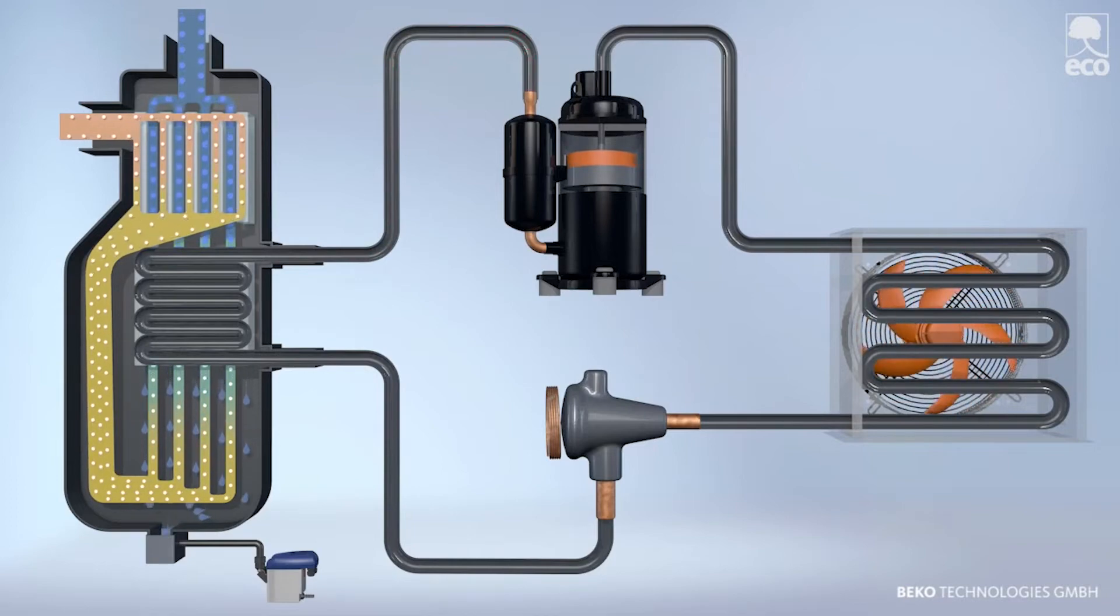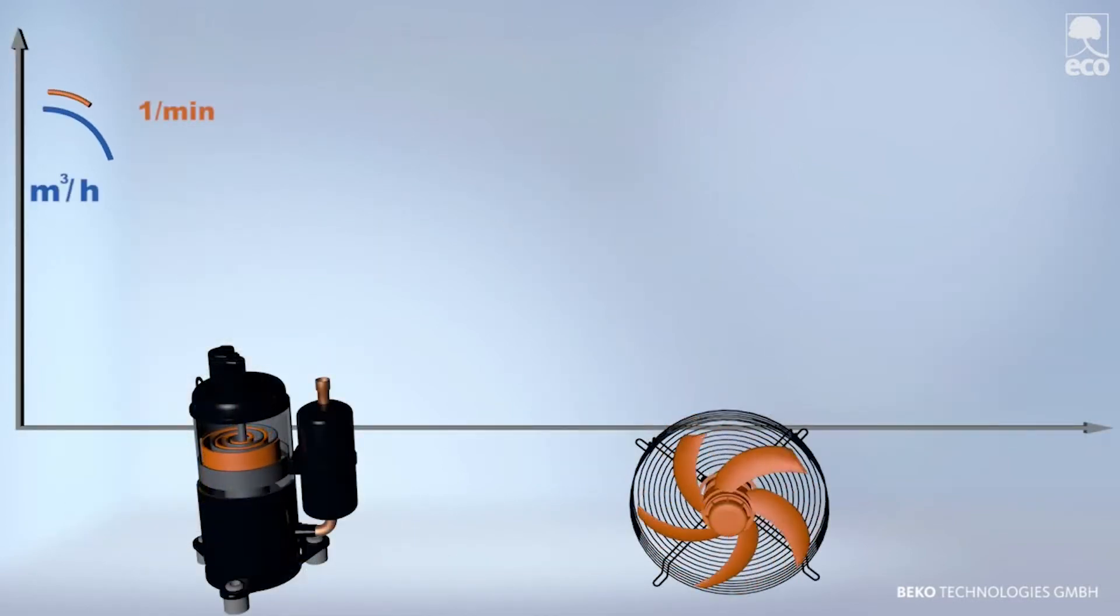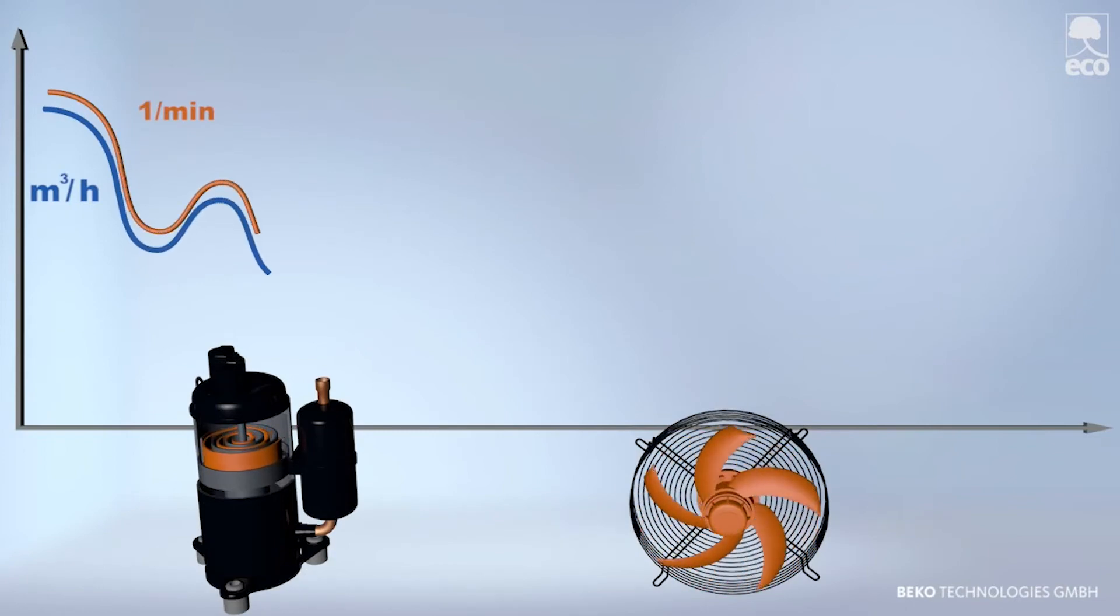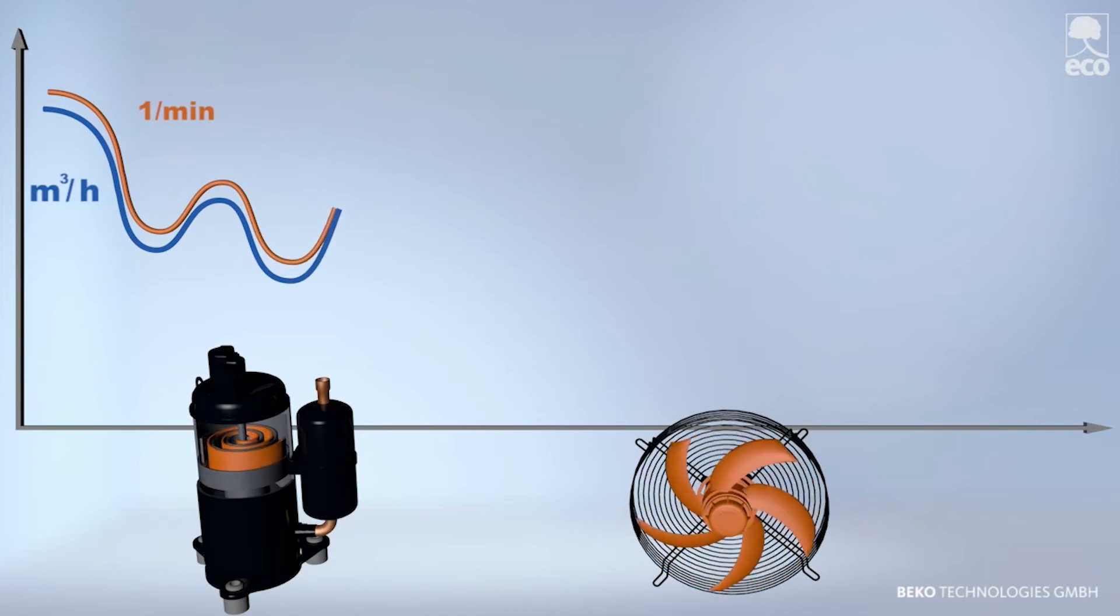In order to save energy when fluctuations in compressed air occur, such as flow volume, temperature, or pressure, the smaller versions of the DryPoint RA Eco switch the refrigerant compressor on and off to accommodate variations in the drying requirements.